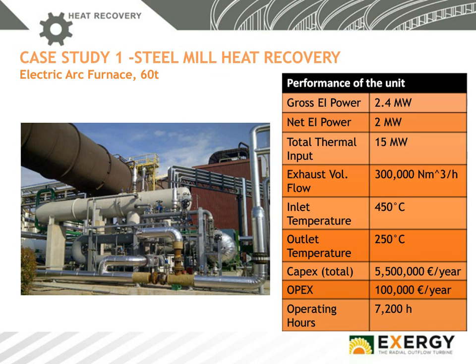They come from a first cooling, in this case to about 450 degrees, and they're cooled down in the heat exchangers to about 250 degrees. The investment needed for this kind of plant is in the range of 5.5 million euro. Sorry for the mistake, it's not per year, it's 5.5 million total. And the operational cost, in euros per year, is in the range of 100,000. We have taken as an example 7,200 hours of operation of the plant, which is a typical number for a steel mill.